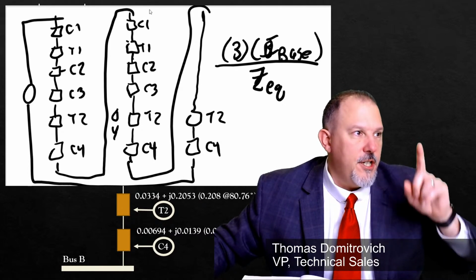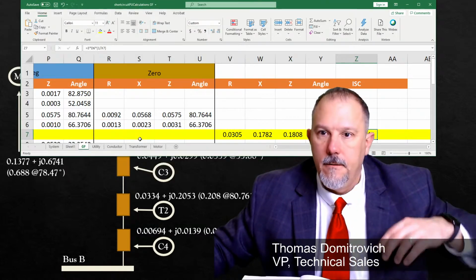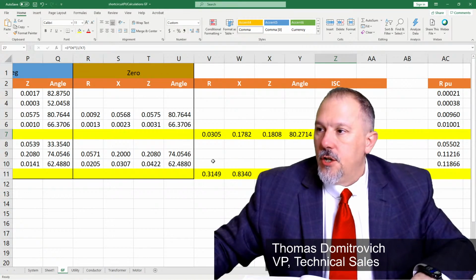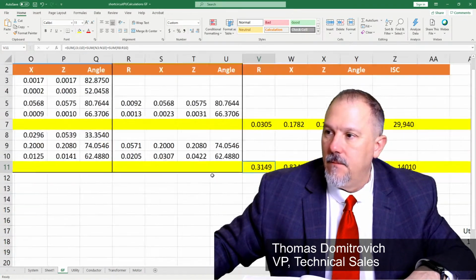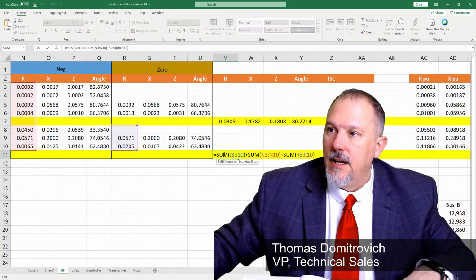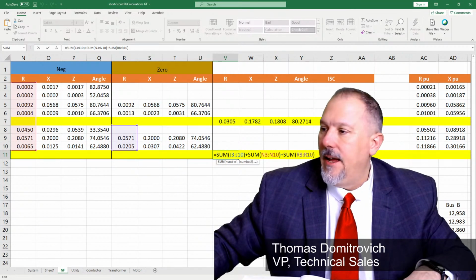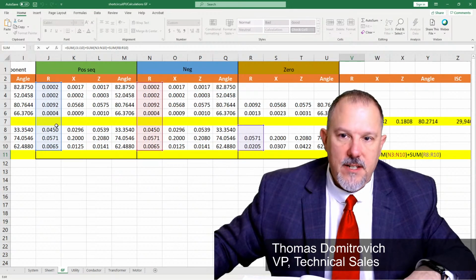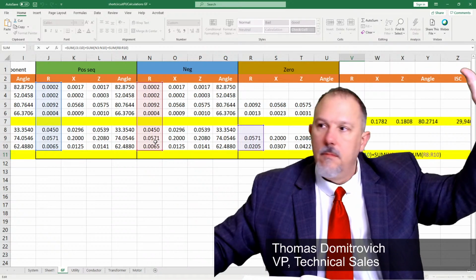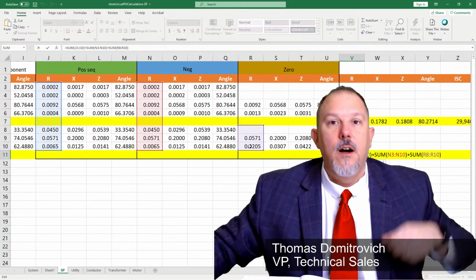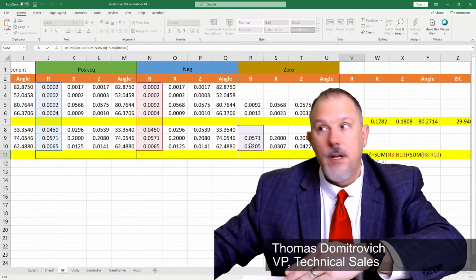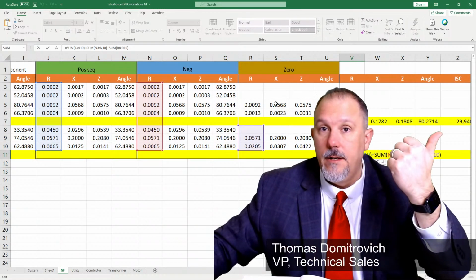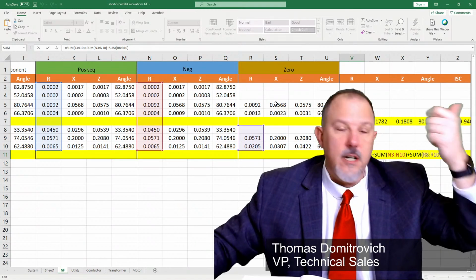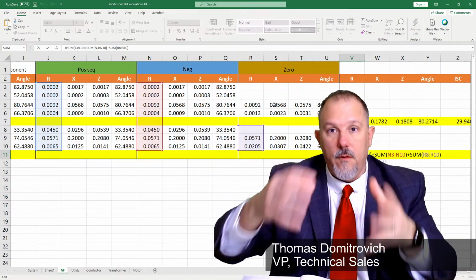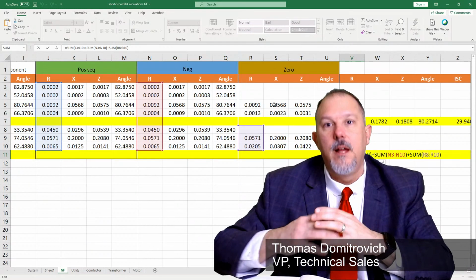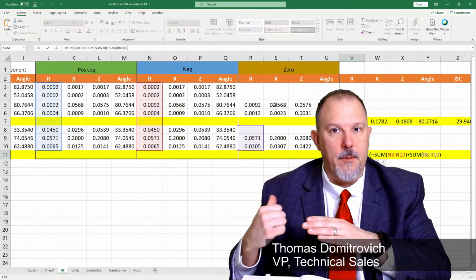Take a look at the spreadsheet that I gave you. Look what I've added in column V for R. I added all of the positive sequence, all of the negative sequence, all the way up, but only the zero sequence impedances of the transformer and the conductor on T2. I don't include the R's and the X's from T1 or conductor 3 or conductor 2, because in my equivalent circuit, the zero sequence currents are going to be trapped by that downstream T2 transformer, primary delta.